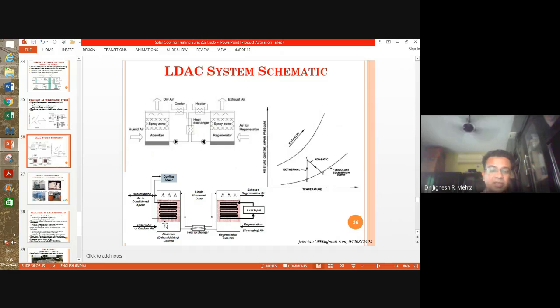So the return air or the outdoor air here is getting dehumidified because of the spray. It comes in contact with the liquid desiccant, and you are also providing cooling with this. So it's possible that you come out in an isothermal process. Otherwise, if you don't provide cooling, it can be adiabatic. So this is reduction of humidity, and along with that, the temperature remains constant, or if you have a good heat exchanger, you can even reduce it while you are dehumidifying. But that's not so easy a task.